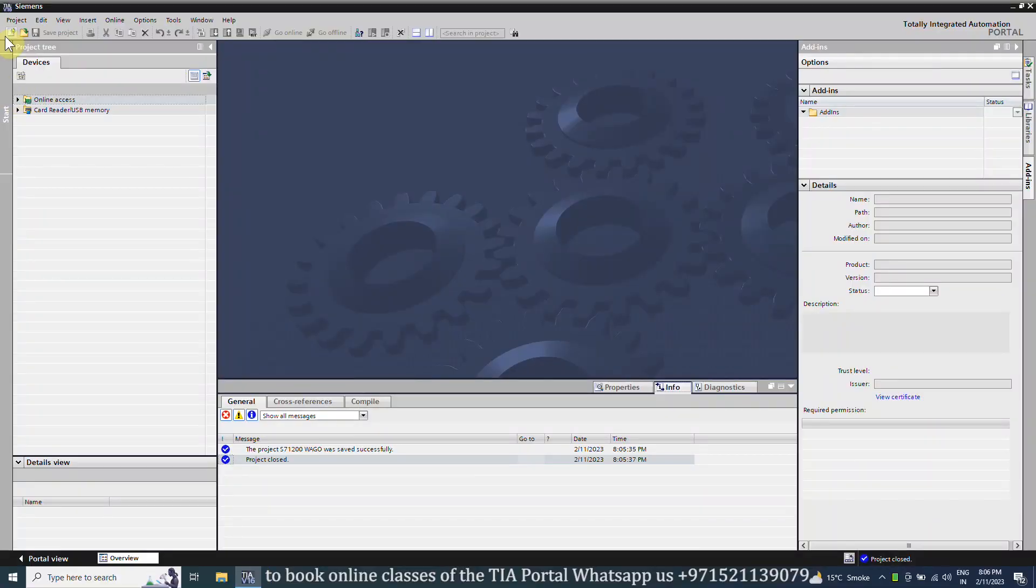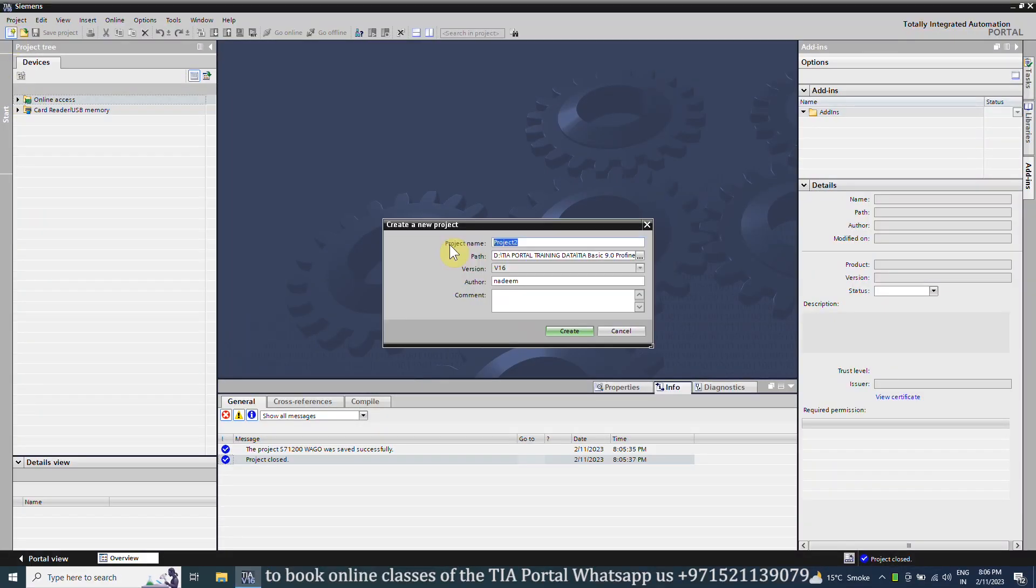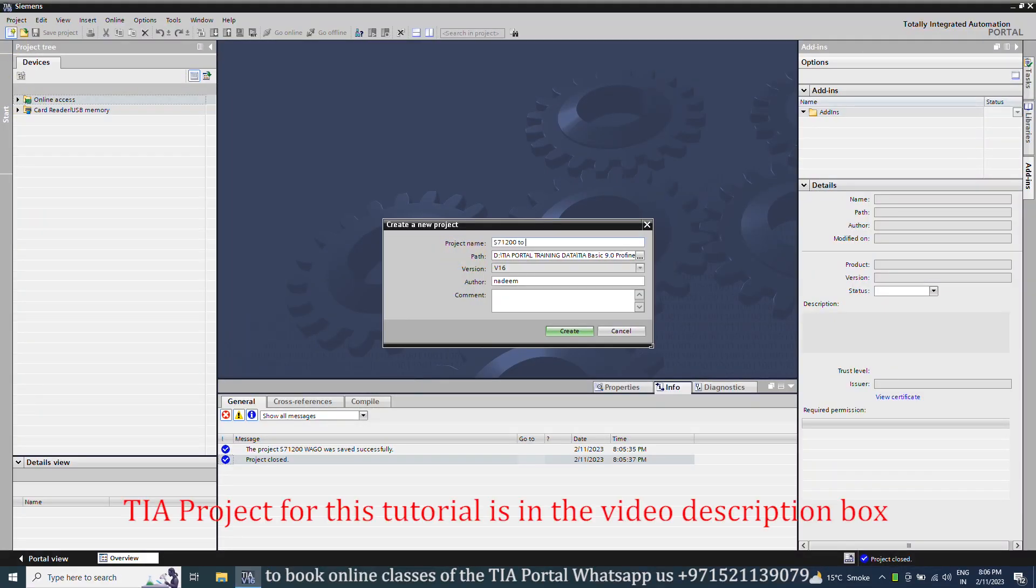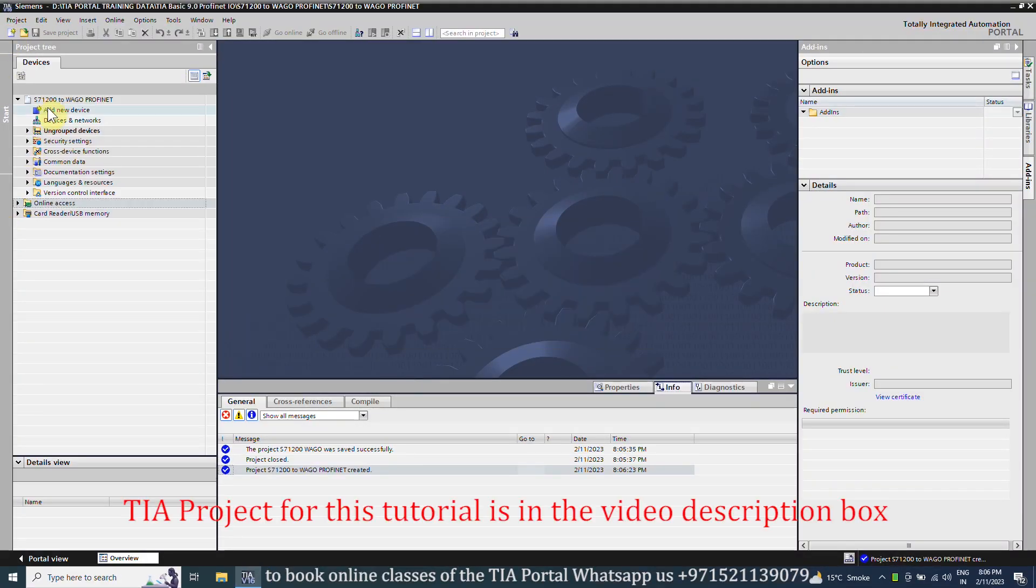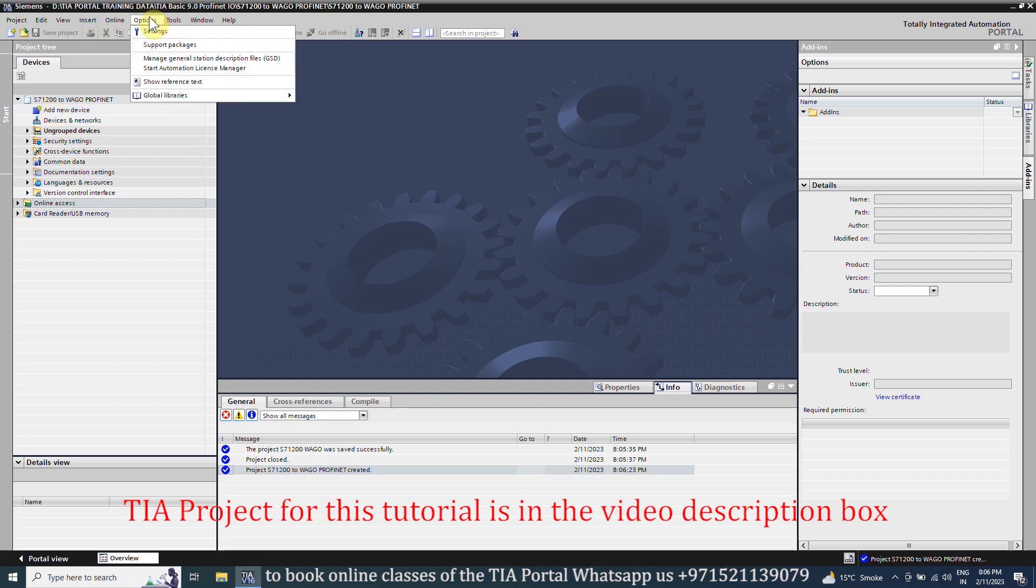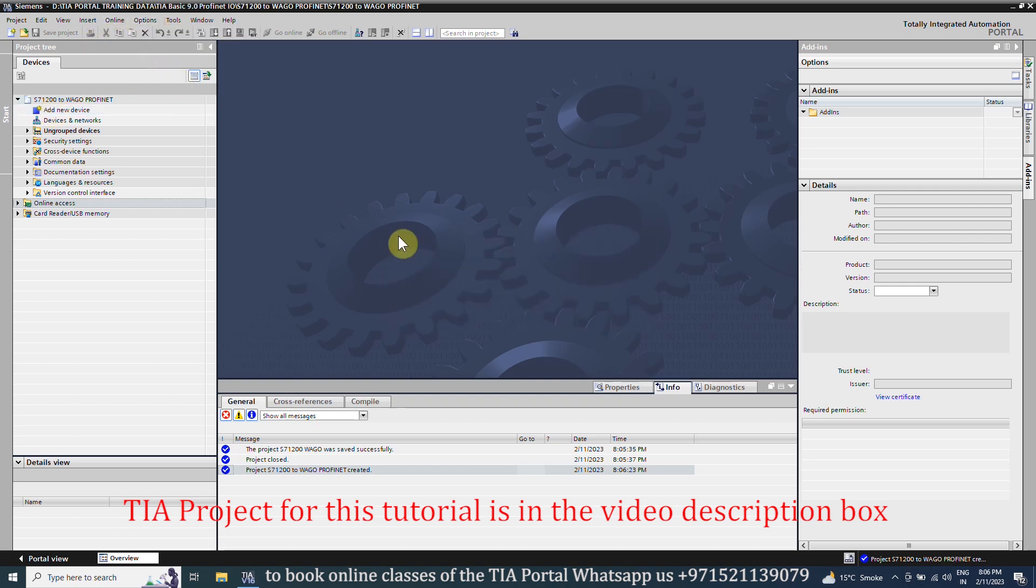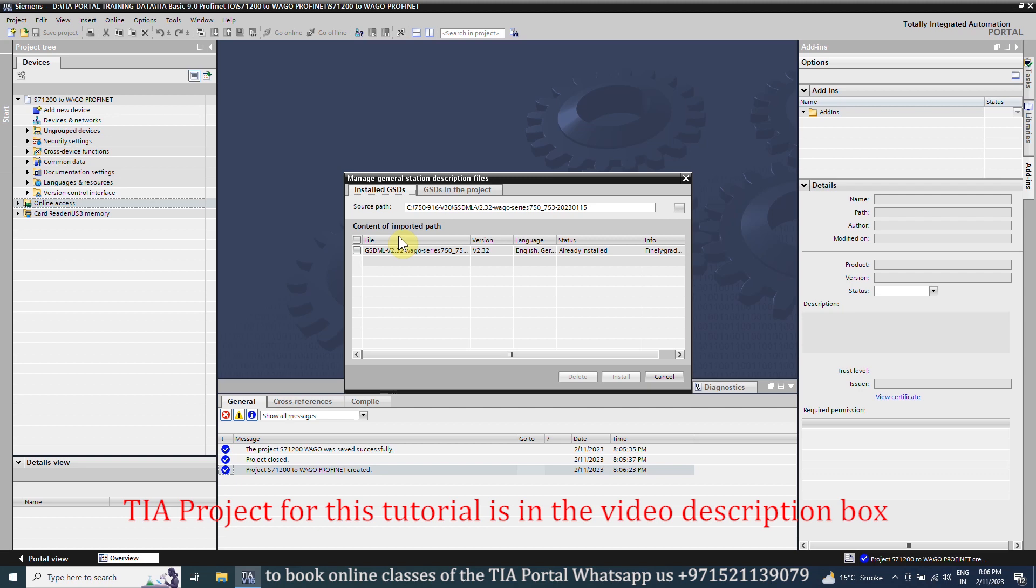Next, we will open the TIA Portal software and create a new project in it. Once the project is created, go to the options menu and click on Manage GSD Files. Here we have to install the GSD file of the WAGO Bus Coupler. Otherwise, we cannot add this module into our project.